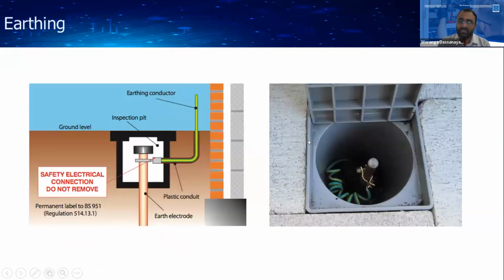So this is how the system is correctly earthed. You have to drive the earth electrode into the earth, and you have to connect your down conductor or the earth conductor to the earth electrode using a clamp, or you can use an exothermic weld as a connection to your earth electrode. So when you are going to the building, you have to clearly examine whether the system is correctly earthed using this proper method.